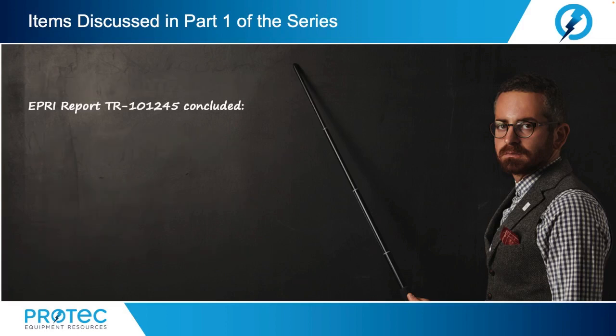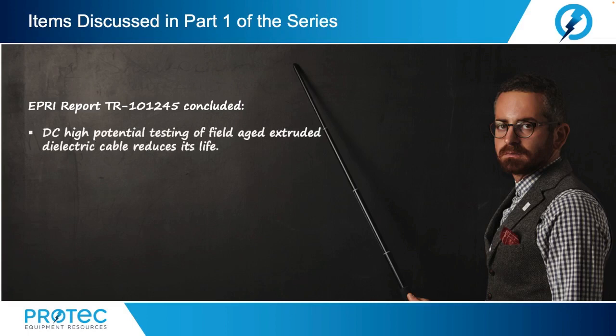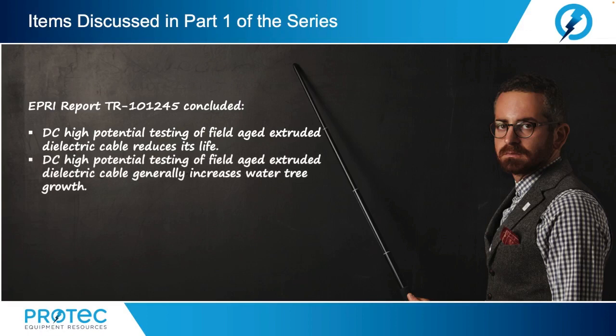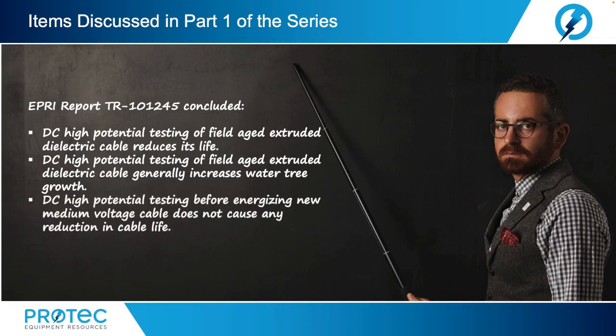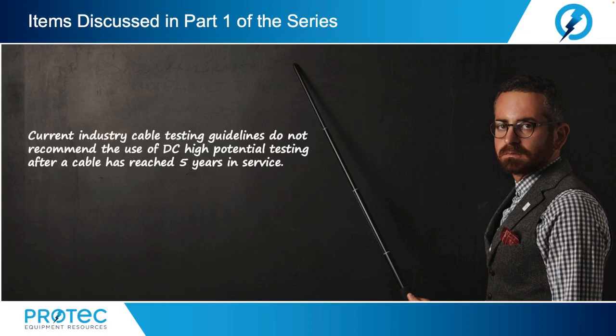In part 1, we also discussed the EPRI report TR101245, and this report concluded that DC high potential testing of field-aged extruded dielectric cables reduces the life of the cable. DC high potential testing of field-aged extruded dielectric cable will generally increase water tree growth. And the EPRI study concluded that DC high potential testing before energizing new medium voltage cable does not cause any reduction in cable life. Now, current industry cable testing guidelines do not recommend the use of DC high potential testing after a cable has reached service life, 5 years in service.